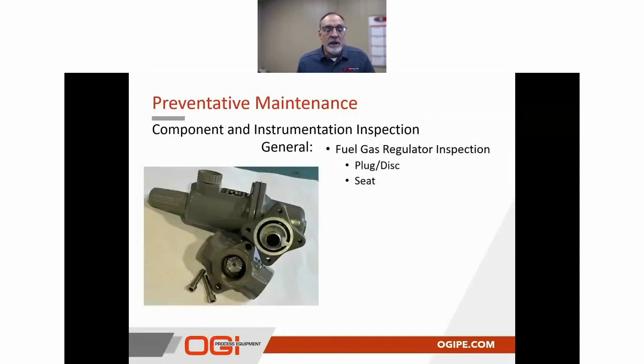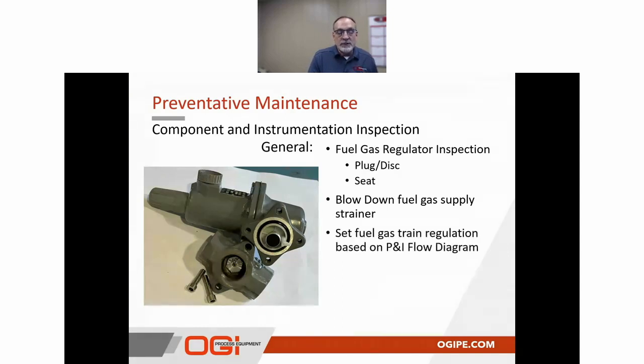From a component aspect, ensuring that the regulation system, the natural gas pressure regulating systems, are properly working. In this case, we'll actually remove the heads of the regulators and inspect the discs and the seat to make sure that they're clean and they're not damaged. We'll also blow down the fuel gas supply strainer to make sure that we free up any potential debris that was captured. And then from there, we'll go in and reset all the regulators to ensure that they're set at the proper pressure set points based on the flow diagram.